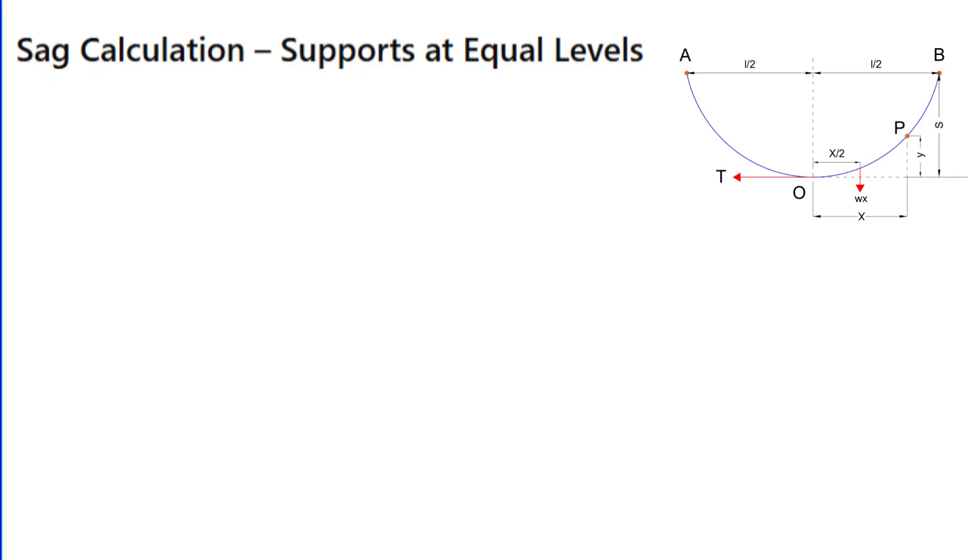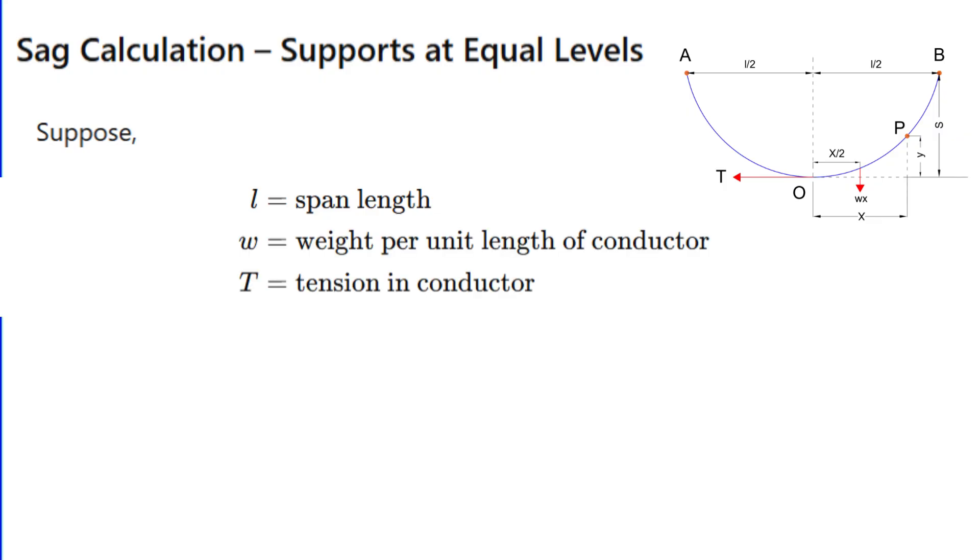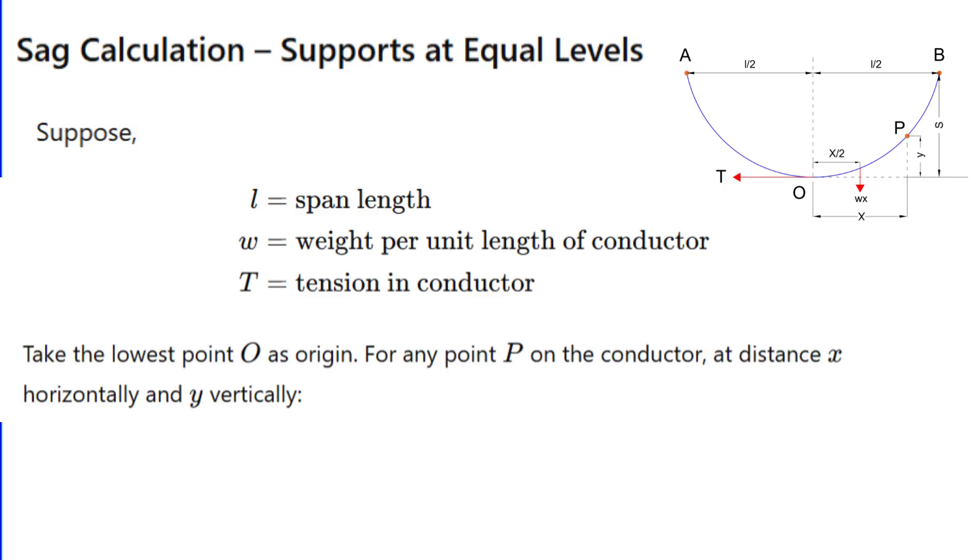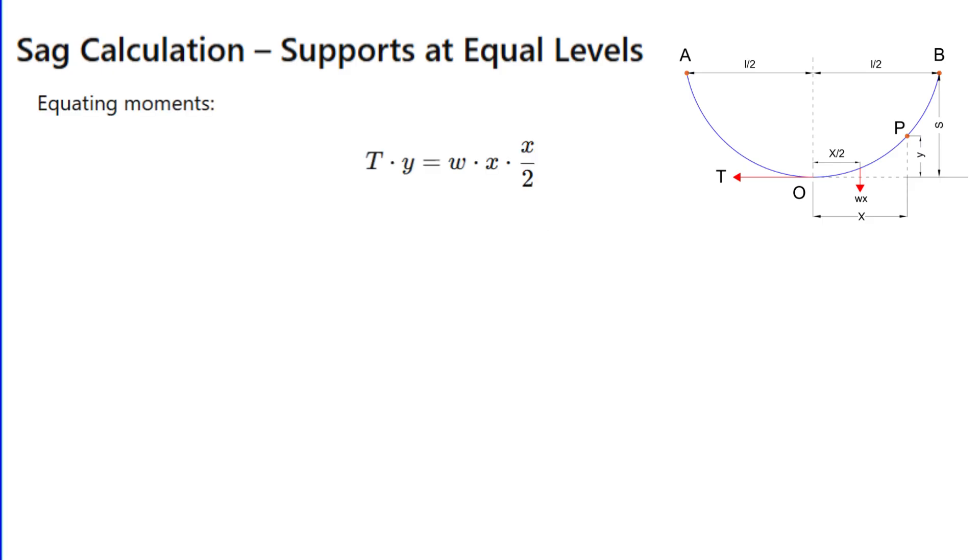Let's derive the formula step by step. Suppose the span length is l, the weight per unit length of conductor is w, and the tension in conductor is T. Take the lowest point O as origin. For any point P on the conductor at distance x horizontally and y vertically, the weight of portion OP is w times x, and this acts at a distance x/2 from O.